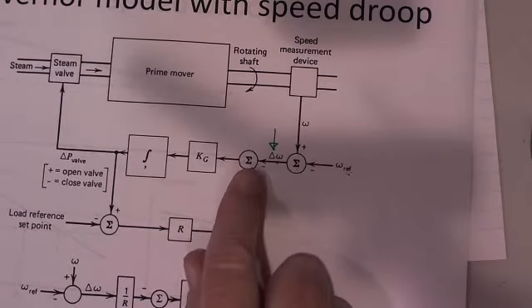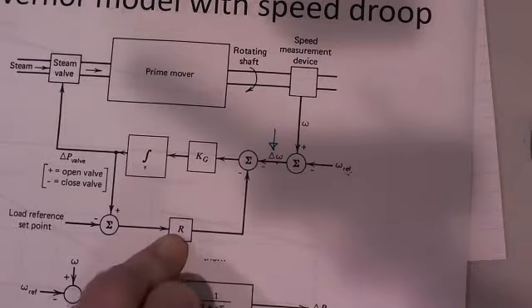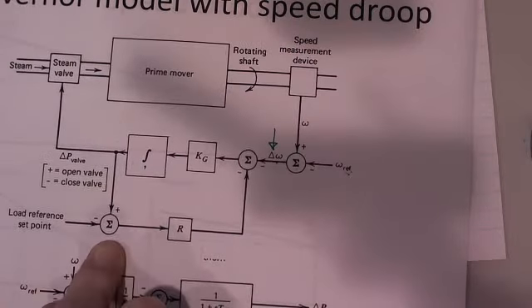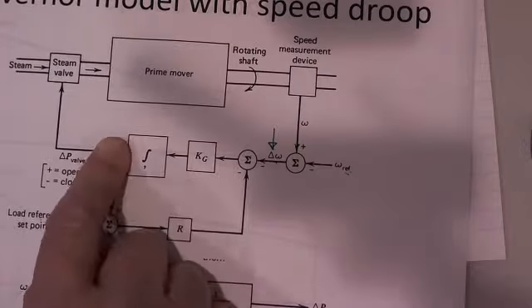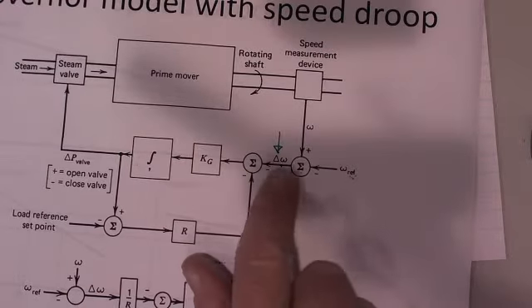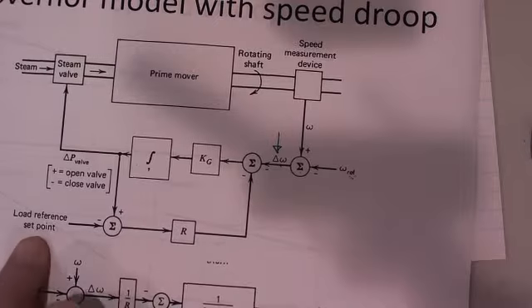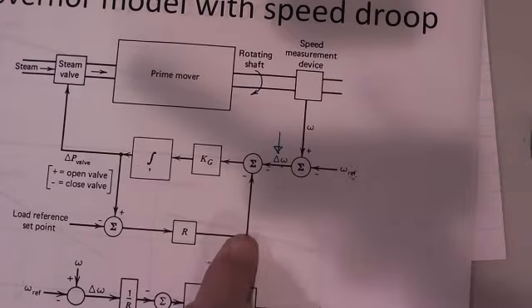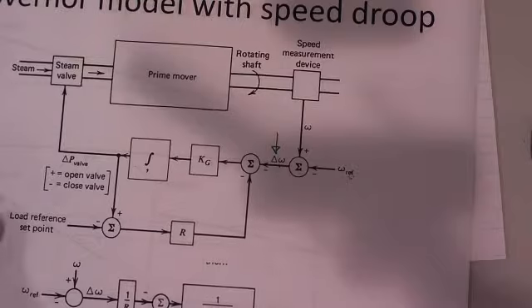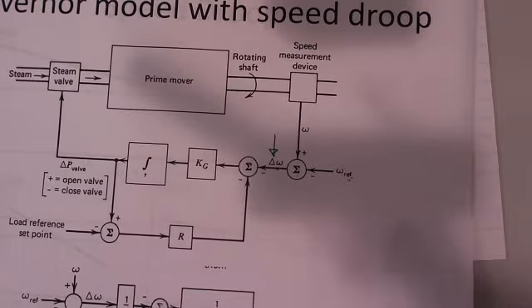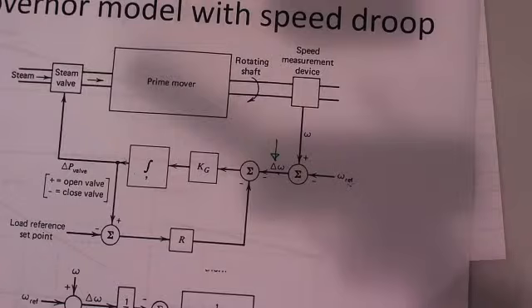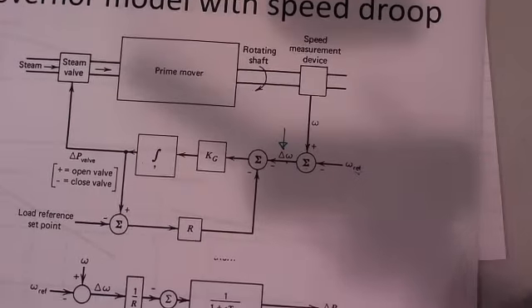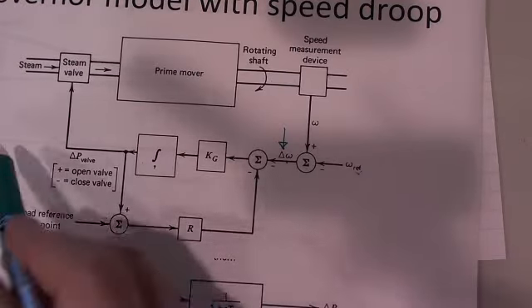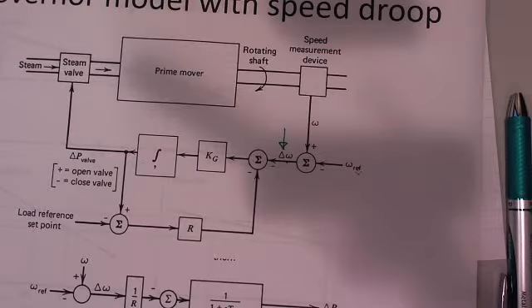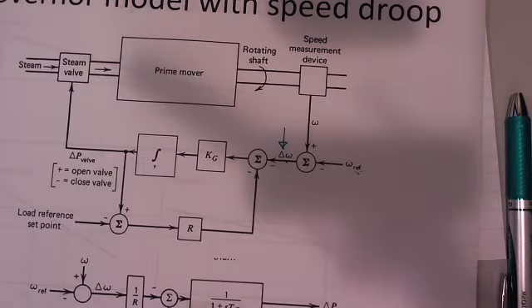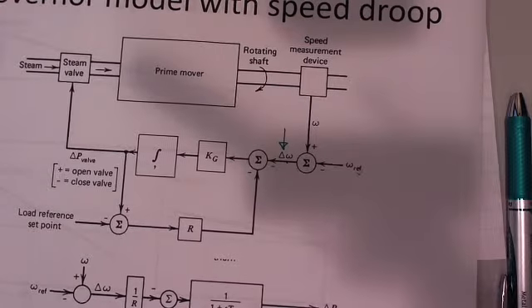And if you took that delta omega and multiplied it by the droop characteristic, you could feed that back in, and you could get the delta omega to look different until you were at the load reference set point. And that was that nice little point that they rested it on, the little point in the diagram of the flyball governor. So this is just the same thing boiled down to a set of equations that you can put into a control.